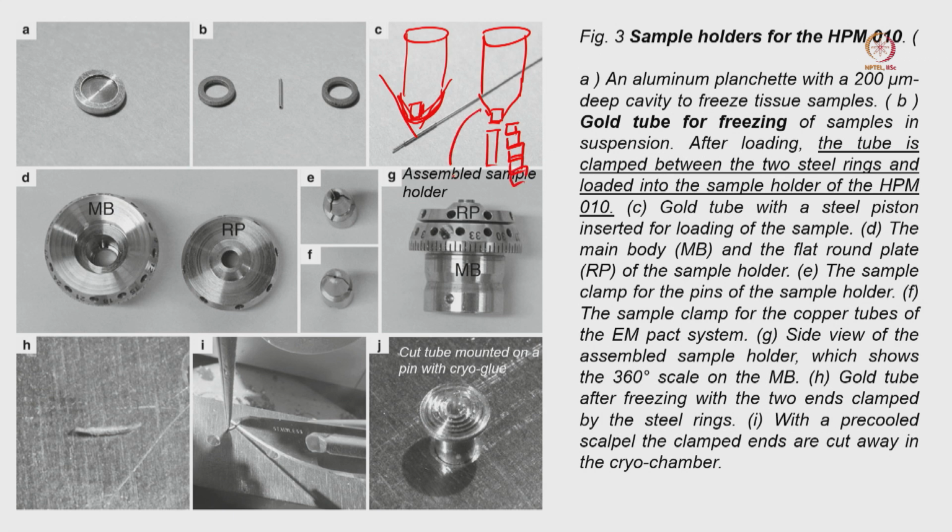This particular part will go inside here, and this is the position we have to change of this tissue or cell in such a way that it can face towards the knife, and it should be very nicely positioned at a 90-degree angle. There should not be any tilt between the knife and the sample. That adjustment we have to do.